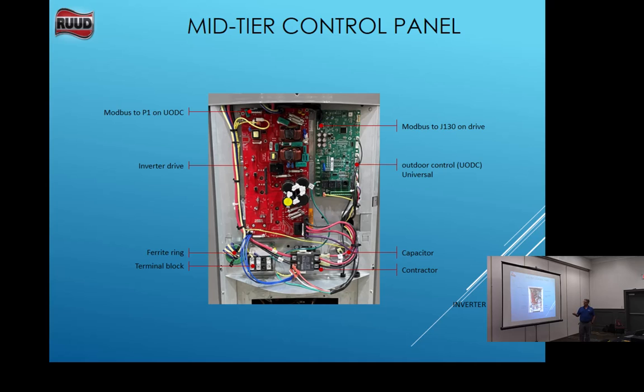What's the one thing we don't ever want to do that we've heard before? Don't push the contactor in. If you push that contactor in, you're going to get a burnt spot right here. Okay? So we don't want to do that. Never. Quick. Smoke comes out. Smoke, yep, can't put smoke back in.